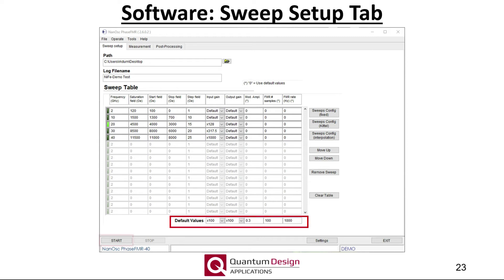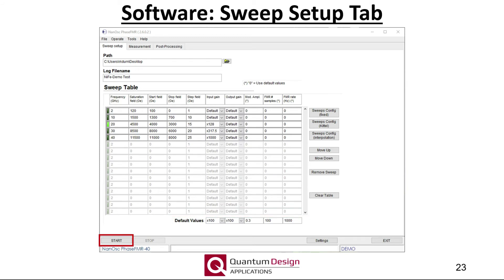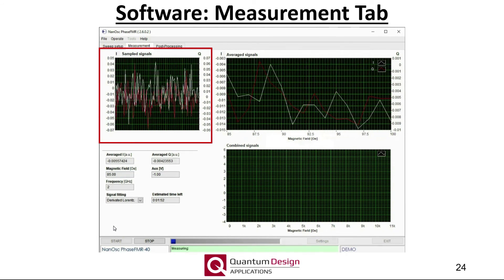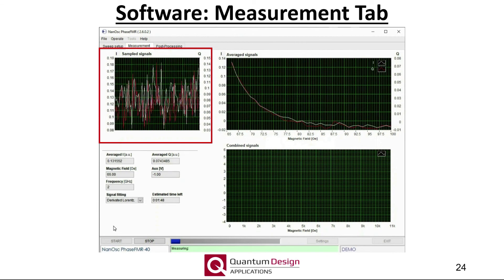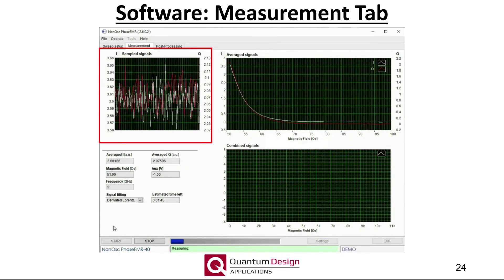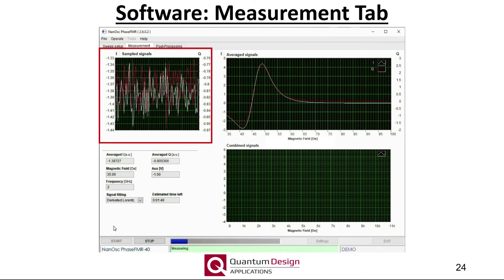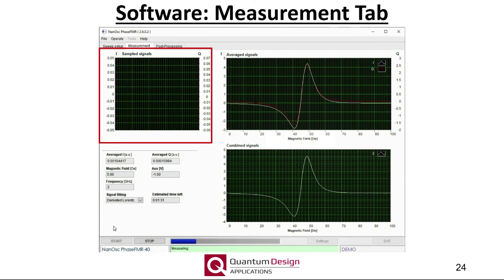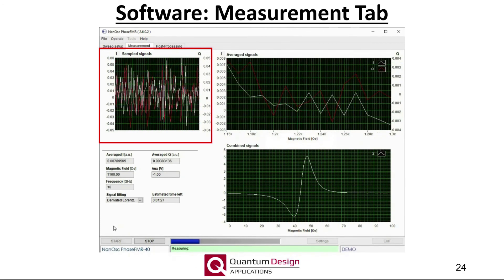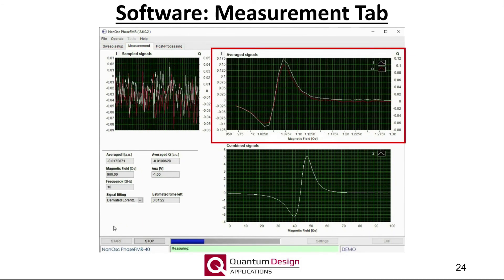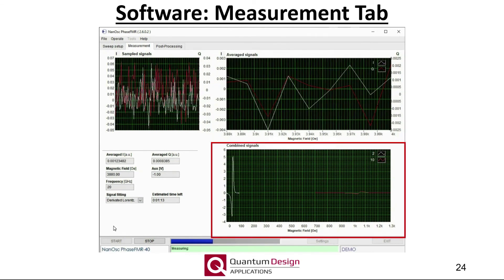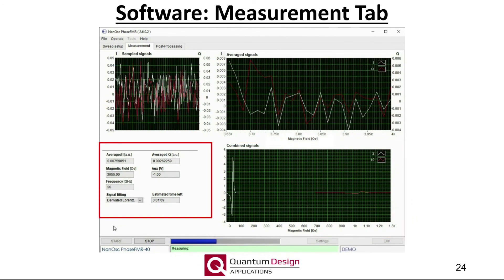Once the sweep table is set, simply click the Start button to initiate the measurement. The software will automatically advance to the Measurement tab. Here we will run through a sample measurement at an accelerated pace. This window shows the measured I and Q channels. Remember, a lock-in technique is used for the measurement, and therefore both the in-phase or I channel and out-of-phase quadrature or Q channel are simultaneously measured. It is also important to note that the phase is relative to the modulation field provided by the Helmholtz coil and in an absolute sense is not important for subsequent analysis. As specified in the sweep table, 100 measurements are taken at a rate of 100 samples per second. Those 100 measurements for each I and Q channel are then averaged together and displayed to the right at the specified measurement field. Once a given field scan is completed, the resultant I and Q channels are combined to find a particular resonant spectrum, shown here.